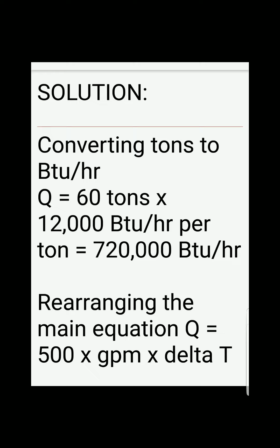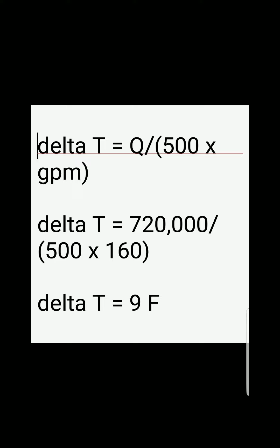So now that we have rearranged the formula, we can substitute the capacity that we calculated earlier, 720,000 BTU per hour, divided by 500 being a constant, and the 160 gallons per minute. And then we will get an answer of 9 Fahrenheit delta T or temperature rise. So that's the answer for the first part of the question.